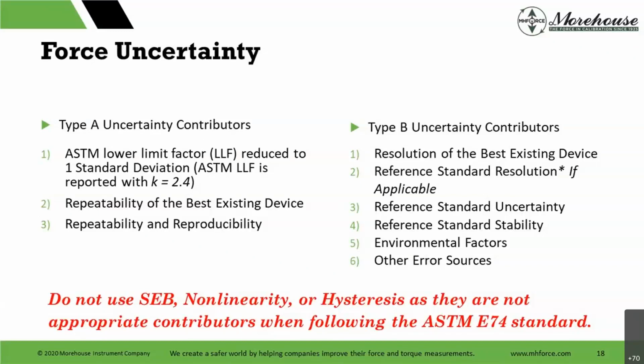So force uncertainty, type A uncertainty contributors, things like the ASTM lower limit factor. That is a calibration standard for force instruments. I encourage everyone to use that standard for force because it is a legal document. There are committees that vote on it, as opposed to someone just saying, hey, do a 3-point calibration and verify it's within tolerance.